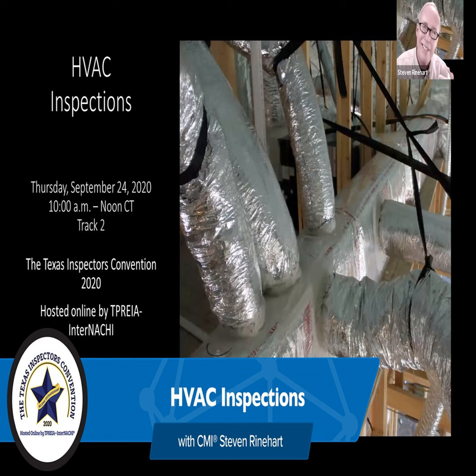Humidity has a lot to do with it. It's nearly impossible to compare apples to apples in different parts of the state with different humidity. High humidity will have lower cooling performance because it's working on the latent heat. Inspecting vacant homes, it's vacant, it's hot, it's humid inside the house. You turn it on, it immediately starts taking the moisture out of the house. It's not cooling. I don't know if you could say you could run it for hours before you stabilize with what it's truly performing, but it's not going to perform as well as one that's occupied and already got most of the moisture out of the house. That's a problem right there.